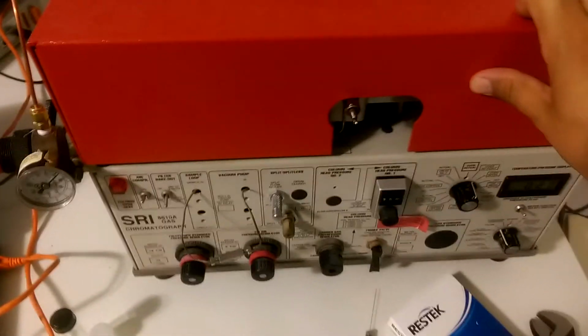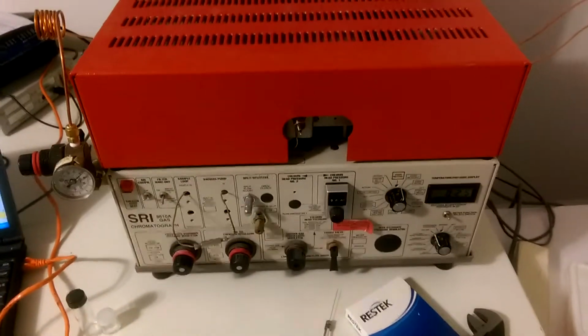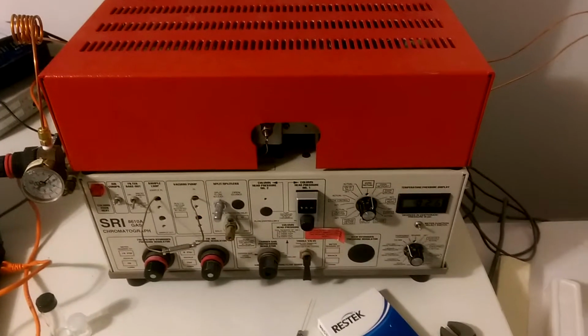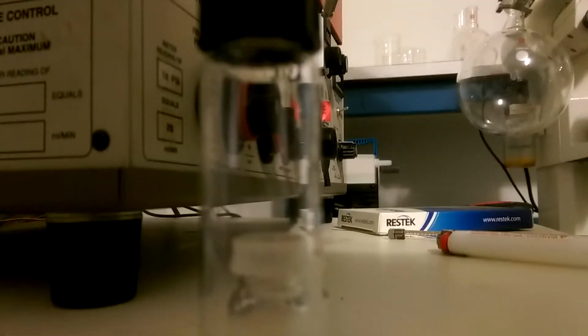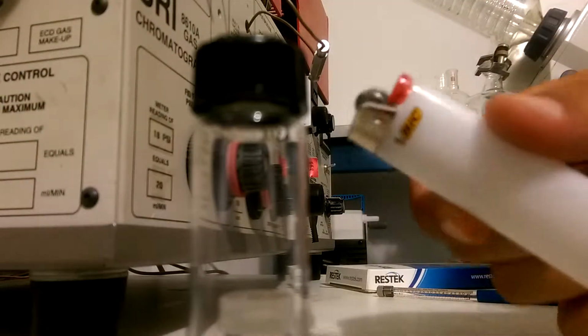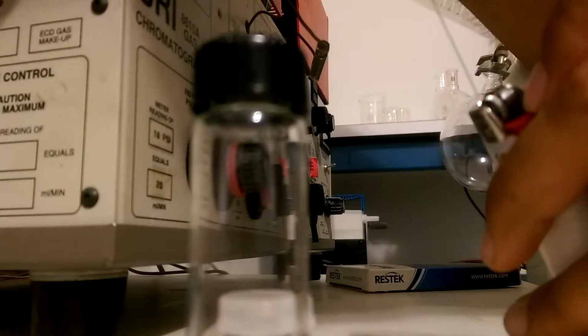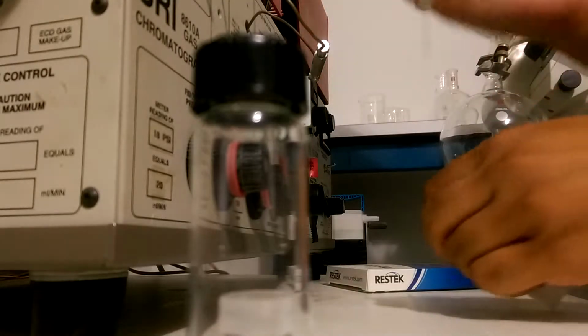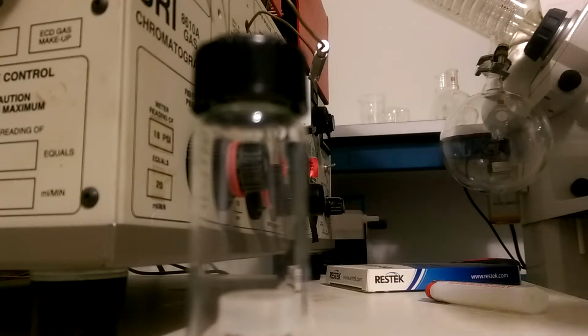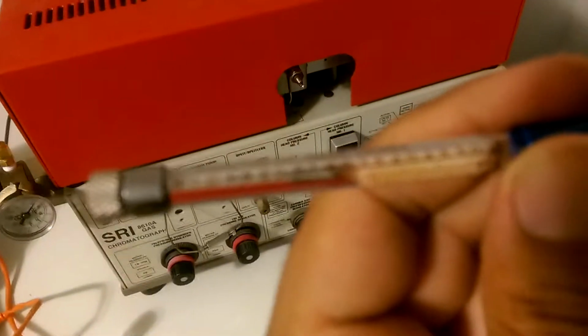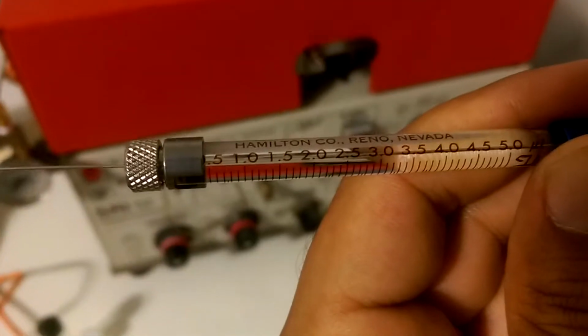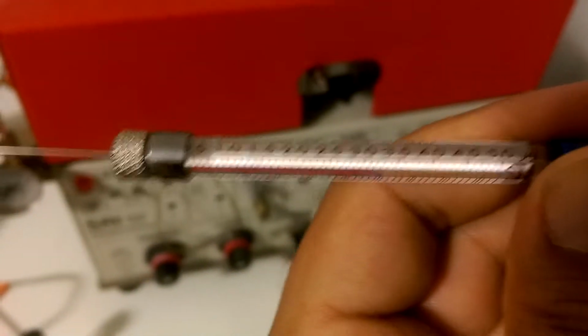What I want to do today was do a quick injection on the unit to show that it's fully operational. I have the FID running currently, so we're going to do a quick butane injection so that you can see that everything on the unit is working just fine. So let me get that set up. I'm going to be taking butane from a simple lighter. Okay, I'm going to be injecting about 2 microliters of butane gas, and then we'll view the results on the computer.